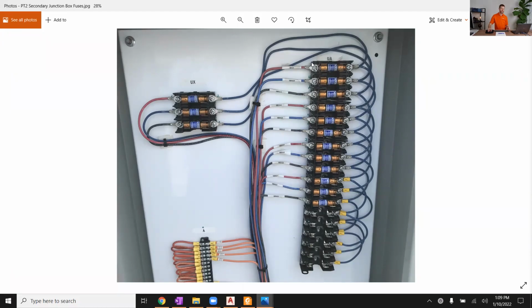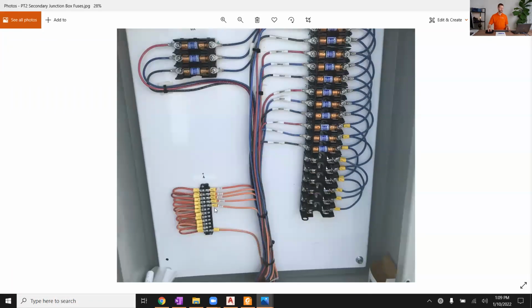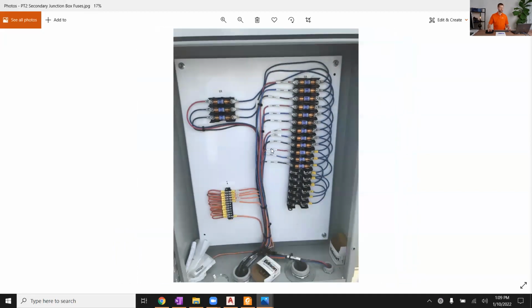And this is now taking A, B, and C phases, A, B, and C, A, B, and C, to multiple relays that need to share the same potential voltage signal. Down here, we've got a common neutral bus. All of these are jumpered together on the neutrals. So this is kind of a little example of a PT junction box. It's a common approach that companies take in their P&C design with potential transformers.